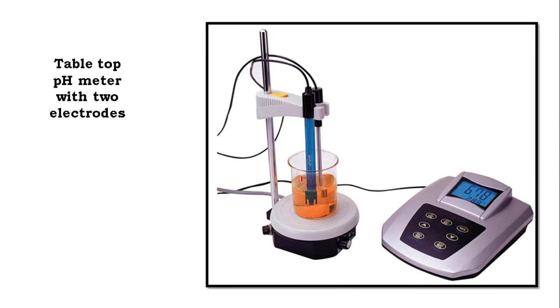Here actually two electrodes are there. One is a pH sensitive electrode here. This is one electrode. One more electrode is there in this meter. We say two electrodes are incorporated into the same package. Battery etc. is provided here. Silver wire coated with silver chloride is there. There is a solution inside, a reference solution. So this system is making up the reference electrode, and here we have the glass electrode.